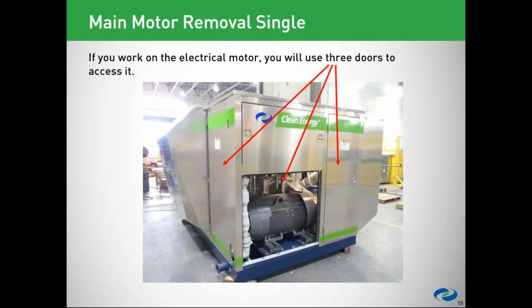Now, I don't have a picture to show it. In addition to this, we have a beam that slides in. So we looked at the hinge support that we had to remove. My apologies, people. This door has to come off, and this corner of the skid has to come off. In behind that little panel is the actual hinge piece that supports the door that has to come out. Then we would remove all of that inlet spool, and we put in a large beam inside of here that will support the motor. We can pick it up and slide it right out through this door on the end.